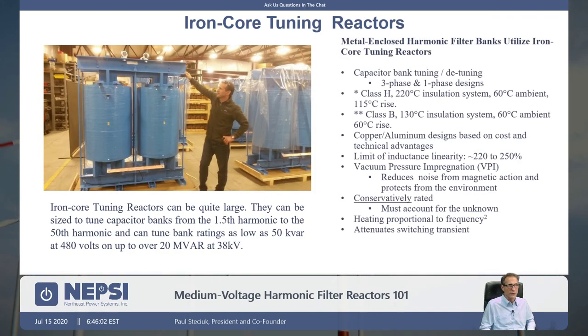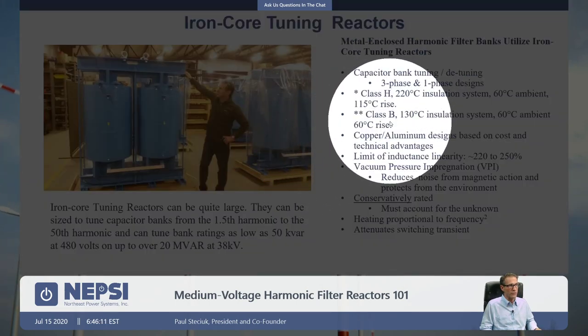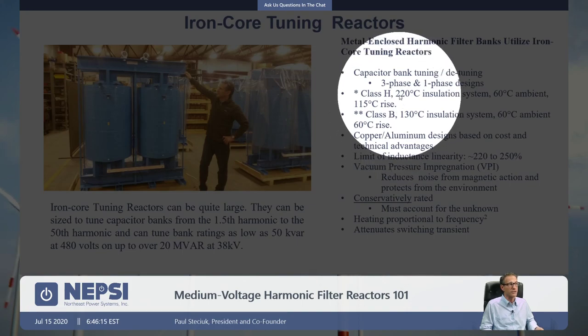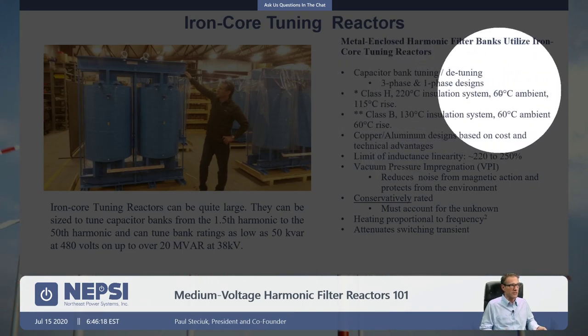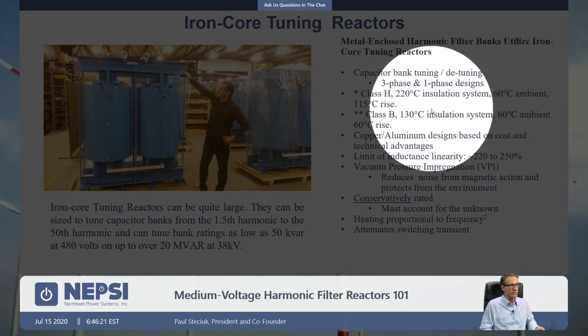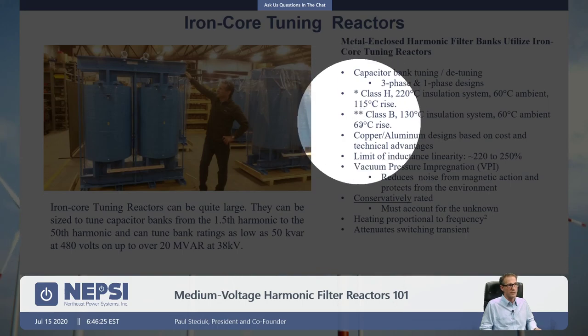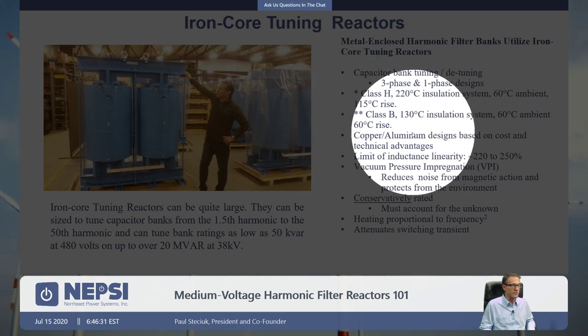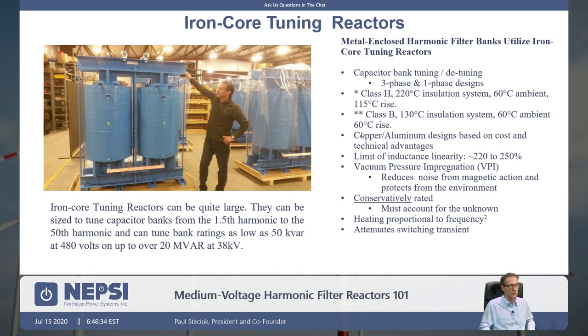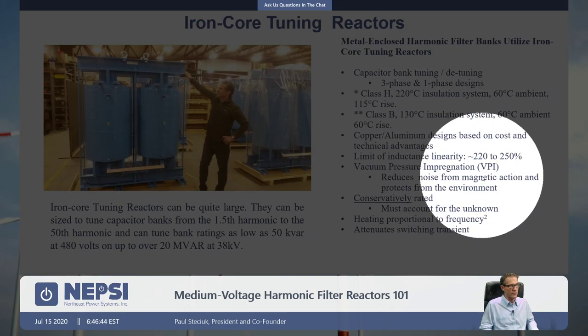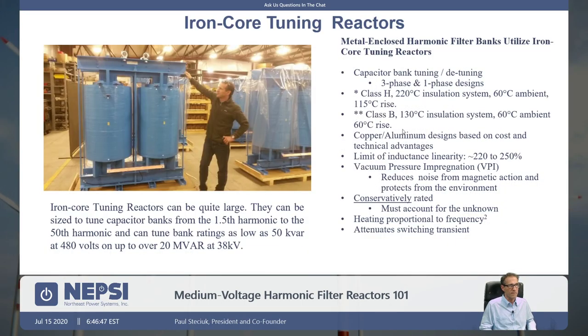Here's a picture of an iron core reactor. You can have different insulation classes — Class H and Class B, 220°C insulation using something like Nomex. Always specify 60°C ambient; the allowed temperature rise is based upon the insulation class. Windings are copper or aluminum — leave this up to the reactor supplier, as they know the economies of scale and what materials work best. Always specify VPI — vacuum pressure impregnation — on the reactor itself.